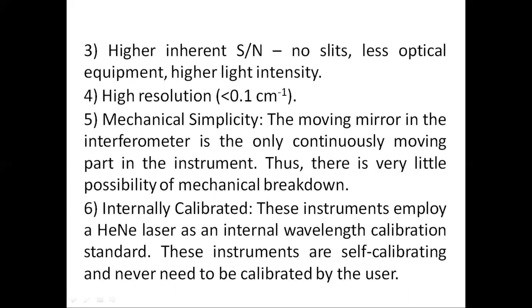Another advantage is that it is internally calibrated. These instruments employ a helium neon laser as an internal wavelength calibration standard. These instruments are self-calibrating and never need to be calibrated by the user. So self-calibration will take place as the monochromatic IR source is there. It itself will calibrate the instrument.